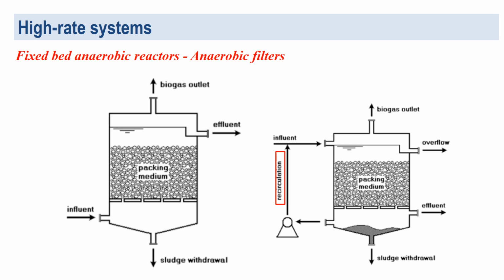the reactor. The main disadvantage of anaerobic filters is the accumulation of biomass at the bottom of upflow reactors, which can lead to blockages or the formation of hydraulic short circuits. In this regard, downflow filters are more suitable for treating wastewater with higher concentrations of suspended solids, as they help mitigate the risks of biomass buildup at the reactor's bottom. This configuration ensures better flow distribution and reduces the potential for operational issues related to clogging or short-circuiting.